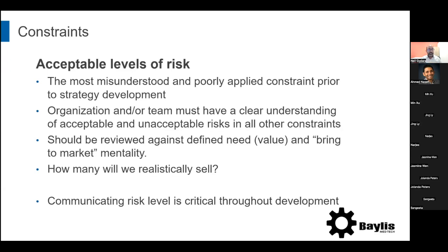It's just information. And the better approach is to build the discipline inside the organization or inside your team, to not be afraid to turn over all the stones, make things fail in development, make things fail in testing, break everything. Don't test parts so they pass, test parts so that they fail. And I'm not saying that's what you submit to your regulatory submission, but you want to learn exactly what the extents of your device are.